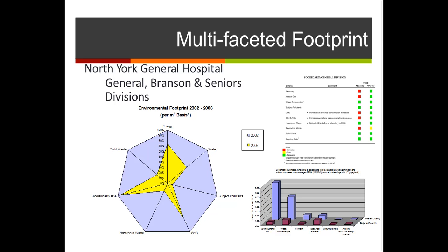You look at it: this is the hazardous waste for the whole hospital. Most of it was actually xylene, formaldehyde, and alcohol, ethanol. So we put a still in the lab, distilled it, and then they use it in the same lab again. So you don't generate the waste, you don't buy it. Based on solvent purchases and hazardous waste, you're saving $25,000 a year with a 1.7-year payback, but it also happened to reduce the hazardous waste by 90% because that was their largest contributor.